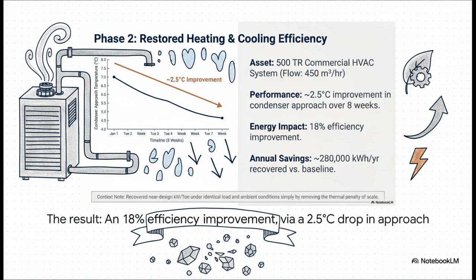So the key number we're looking at is the condenser approach temperature. You can think of it like a report card for your chiller's efficiency. A lower number is an A+. Well, over 8 weeks, it dropped by 2.5 degrees Celsius. And that translates directly to a massive 18% improvement in the chiller's total energy efficiency.